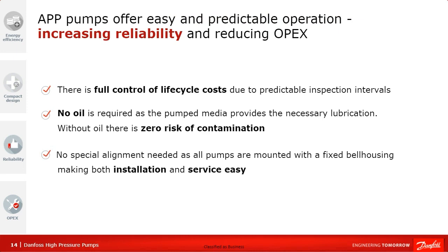APP pumps offer easy and predictable operation, increasing reliability and reducing OPEX through full control of lifecycle cost and service intervals. All wear parts have specified service lives, so service costs are fully controllable. There is no oil in the pump — no oil changes, no lubrication needed beyond what is provided by the pumped fluid — so there is no risk of water contamination. No special alignment is needed as all pumps are mounted with a fixed bell housing, meaning when you reinstall after service there is no risk of misalignment — the motors always align perfectly.